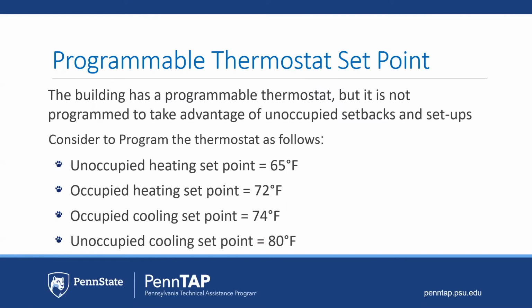I wanted just to have one caveat about set points, which is to make sure you understand your equipment. What is your equipment rated for temperature-wise? I have a personal experience where in my home in southwestern Pennsylvania, it can get below 0 here. I had my setback set too low for overnight, and my furnace wasn't able to successfully kick back on due to the top part of my flue cooling down beyond what my furnace could keep up with. This created a pressure difference within my flue, and my furnace would trigger a safety shutdown because the fumes from my fuel were settling low by my CO sensors.